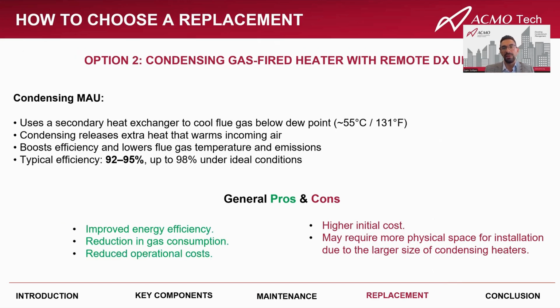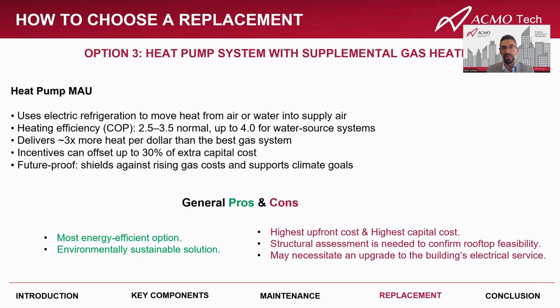The second option is very similar to option one, but now it is a condensing type of gas-fired heater where the secondary heat exchanger is used to cool those flue gases, which then increases the efficiency of the unit drastically. And it does go up to 90 to 95% efficient. Reduction in gas consumption and lower operation costs are some of the pros. And the cons of this option are higher initial costs and the bigger footprints of these units due to a bigger heat exchanger.